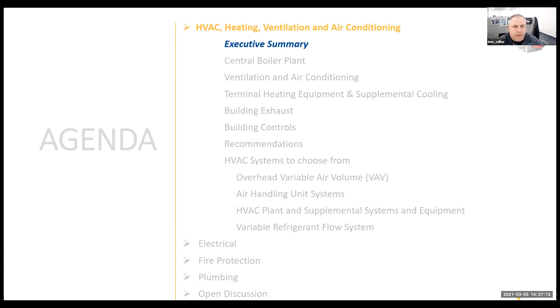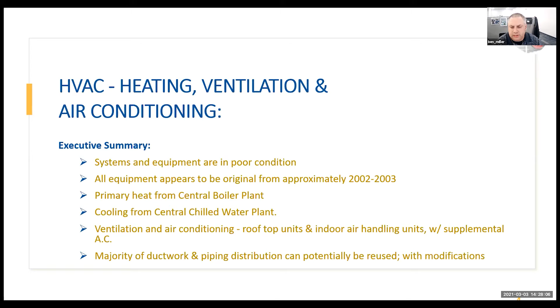So, heating, ventilation, and air conditioning equipment: the systems and equipment are in poor condition, especially in the boiler plant. All equipment appears to be original from 2002 and 2003 when the building was built. Primary heating is from the central boiler plant, cooling is from the central chilled water plant, and ventilation and air conditioning come from rooftop units and indoor air handling units with supplemental AC. The majority of the ductwork and piping distribution can potentially be reused with modifications.